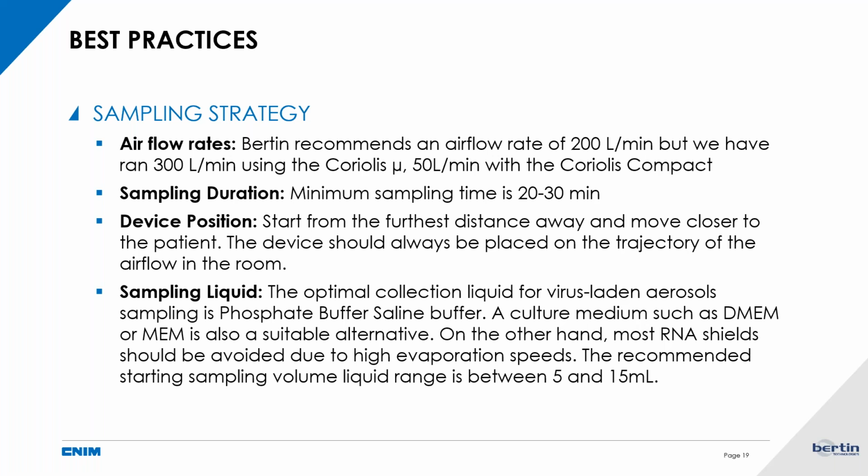You have to consider also that there is a natural movement of the air in the place where you are sampling. And so small particles or droplets generated by the patient are going to be also aspirated by this internal flow. So it's better to check the air movements in the site where you are sampling and find the best positioning for your device.